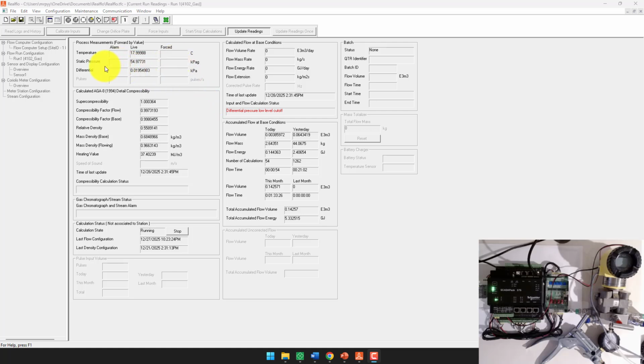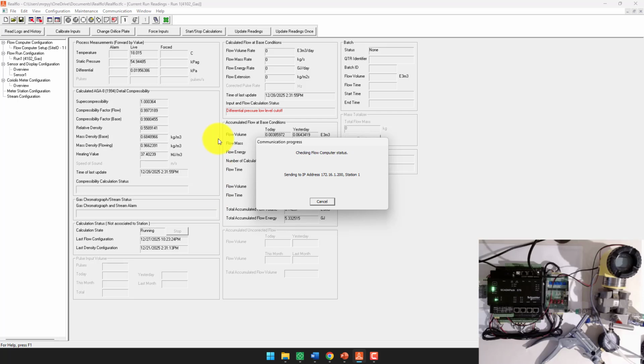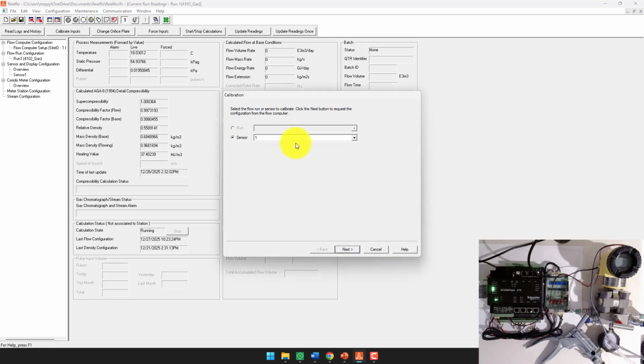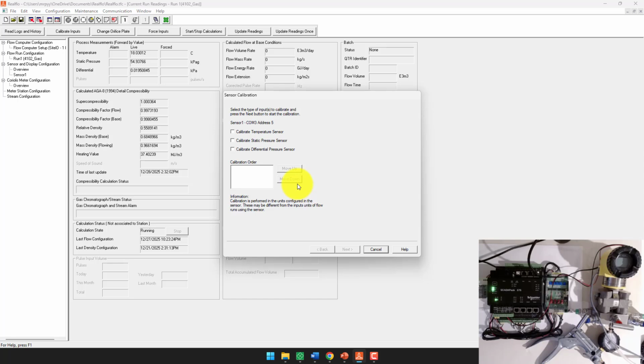In the previous video, we pumped up the static and differential pressure, and one thing you might have noticed is that they're not quite reading zero, so we'll go through how to calibrate those to zero. If you go to calibrate inputs, you pick your sensor. I only have one sensor connected, so I just pick sensor 1, but if you have a few, you need to make sure you're calibrating the right sensor. We'll start with static pressure, so I'll select static pressure and hit next.